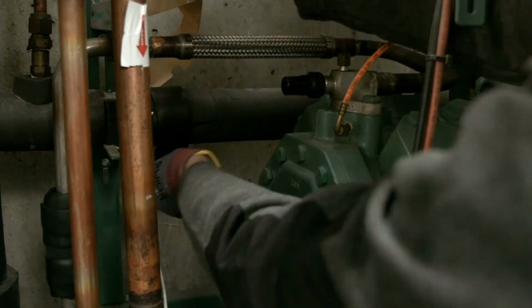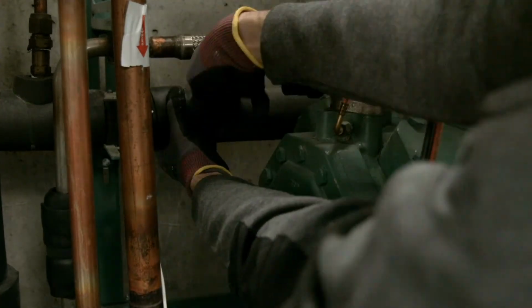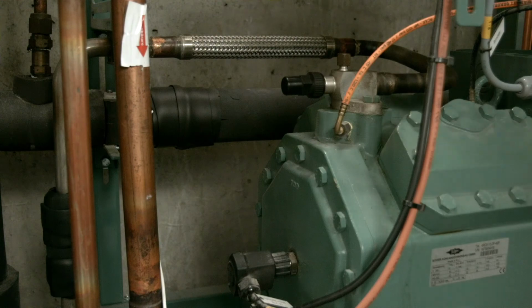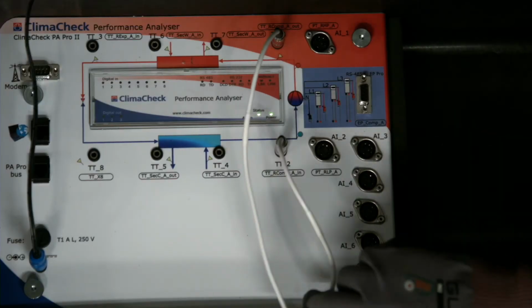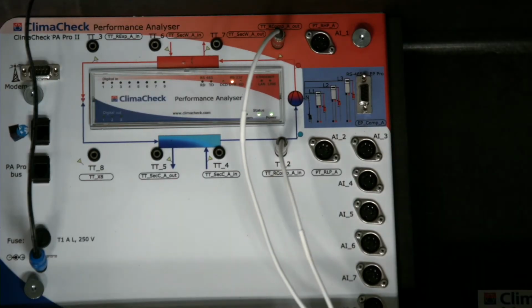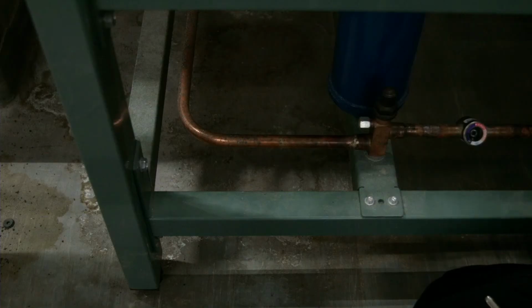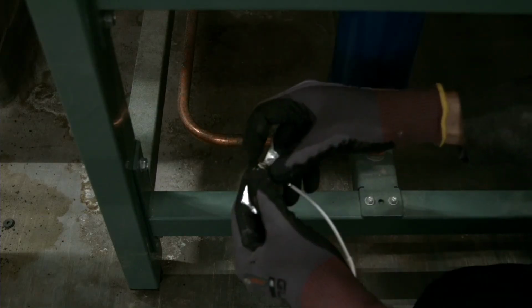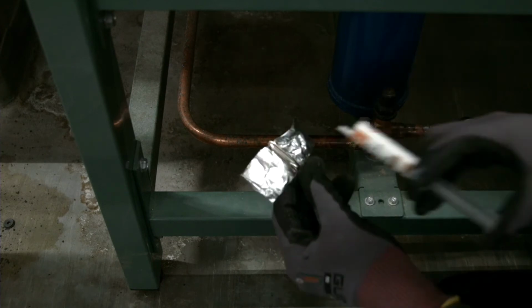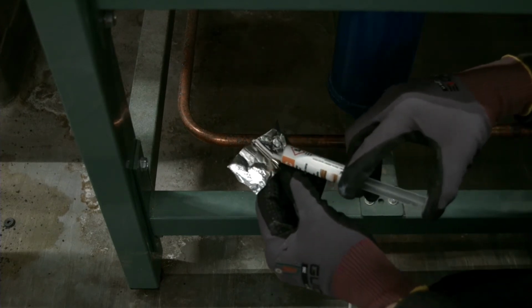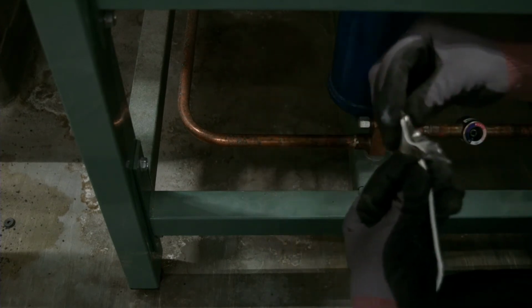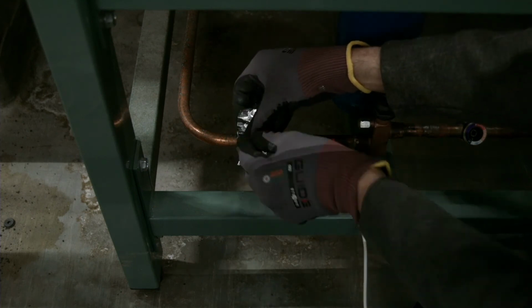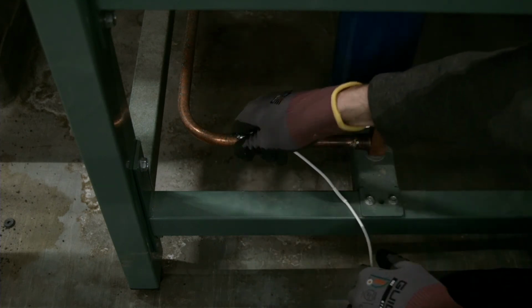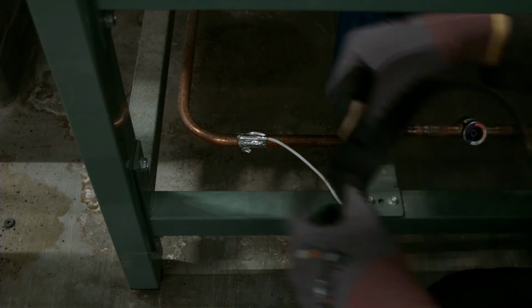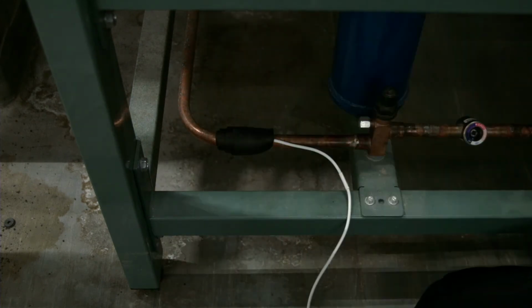Each sensor takes only a few minutes to connect. This one has just been plugged in on the suction line of the compressor. There's a diagram on the ClimaCheck portable unit with clearly marked indications as to where each temperature sensor should be plugged in. This temperature sensor is being fixed to the liquid line just upstream of the expansion valve, again with insulation being applied. And plugged in.